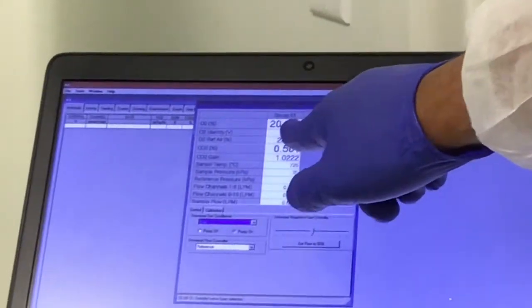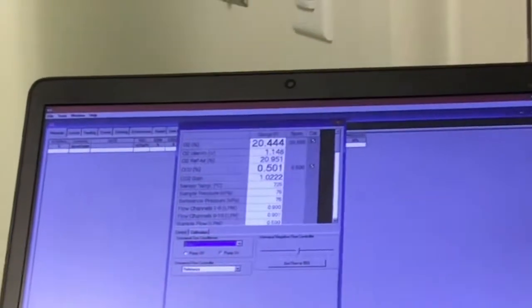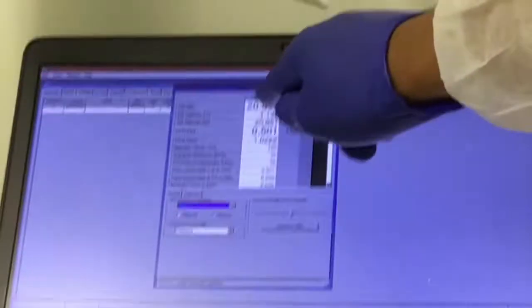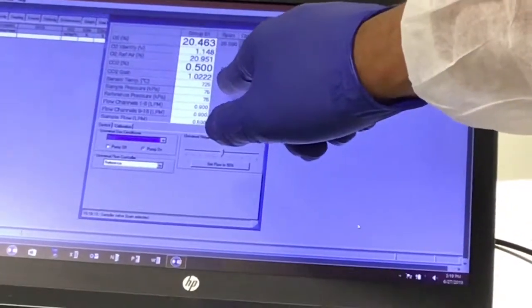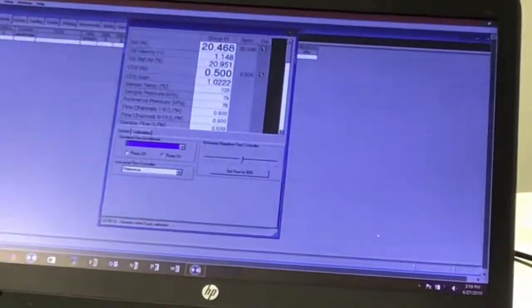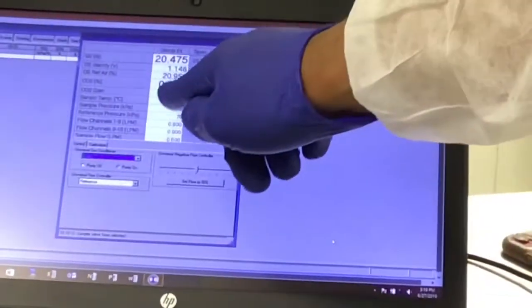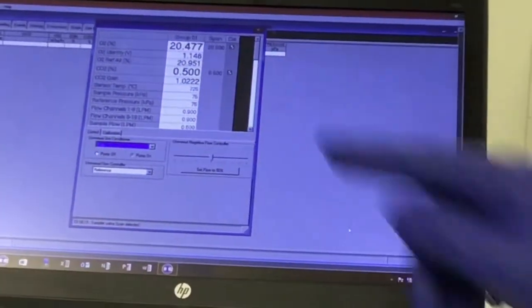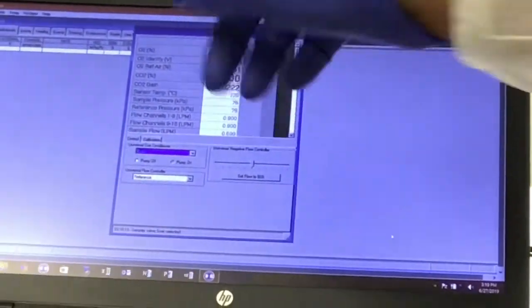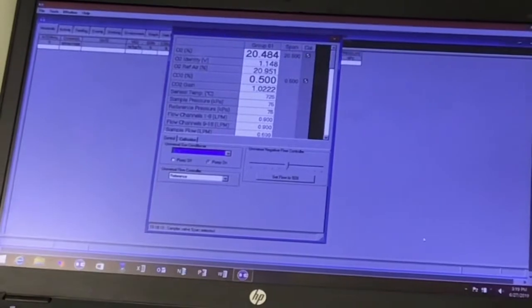So we said our concentration was 20.5. If I am not reaching 20.5, I'm not happy. I would say there's something wrong with this sensor or the gas must be wrong. If I am not within 1% of it, already rounded, of 0.05, either the gas is wrong or there's something wrong with the sensor. The CO2 is always more accurate. The O2 takes time, but 20.5, 20.48, guess what? I am well within 1%.